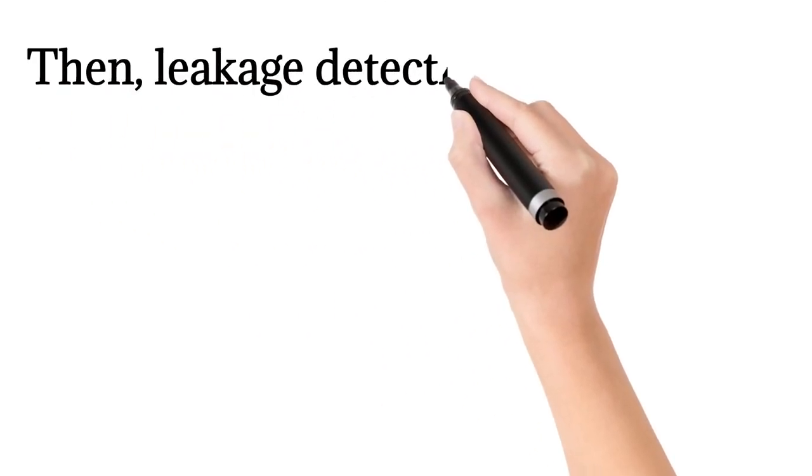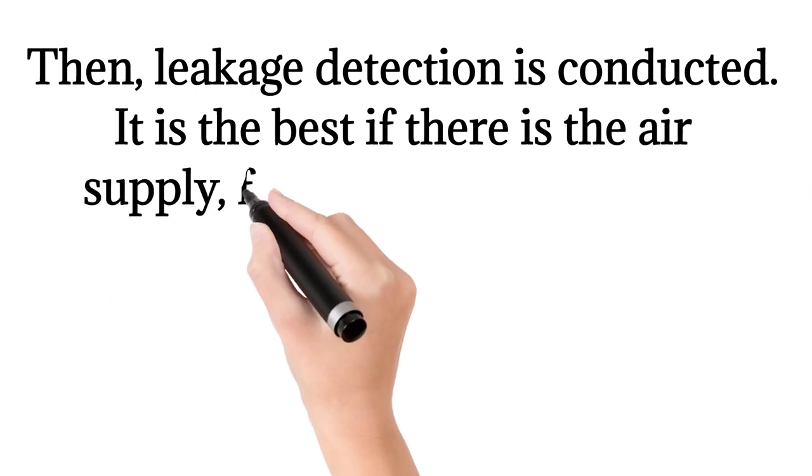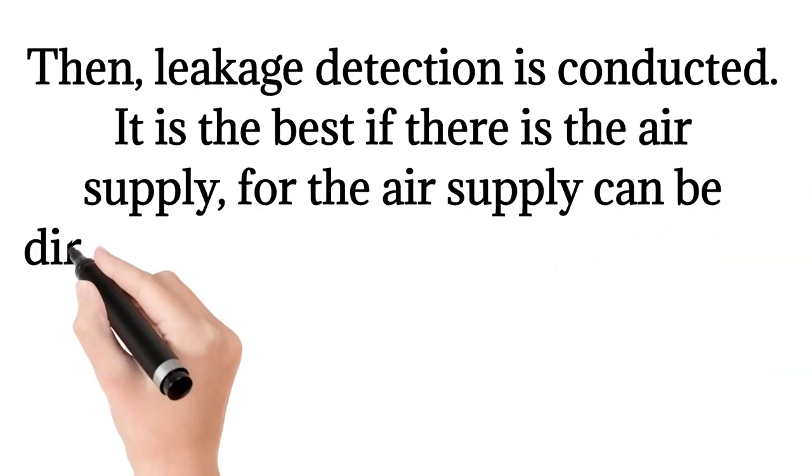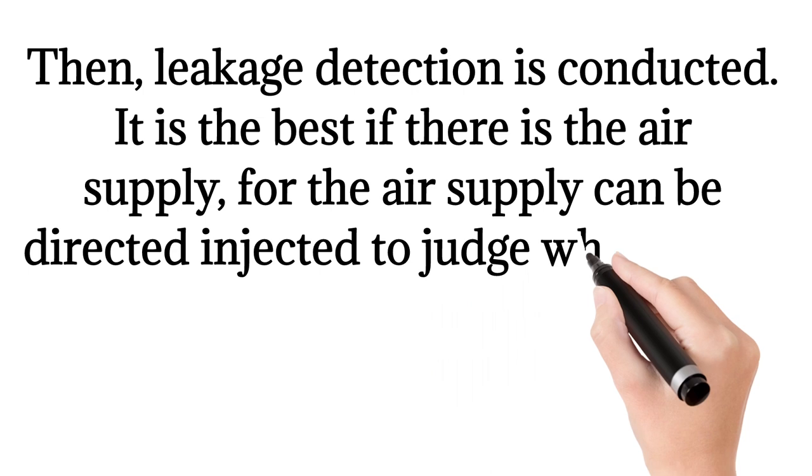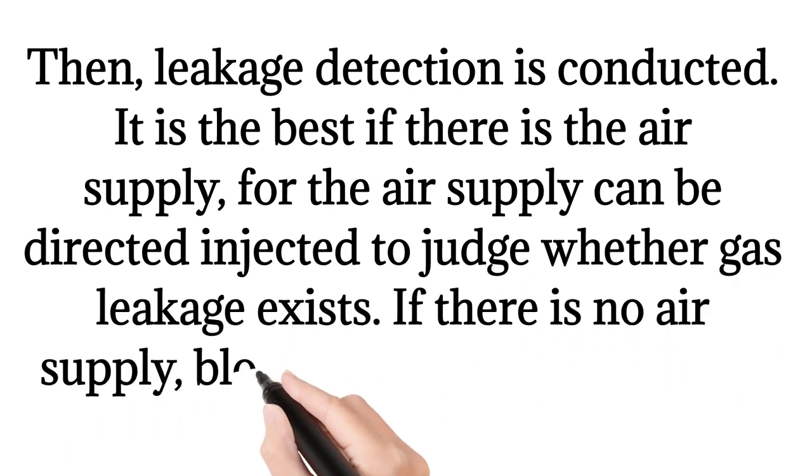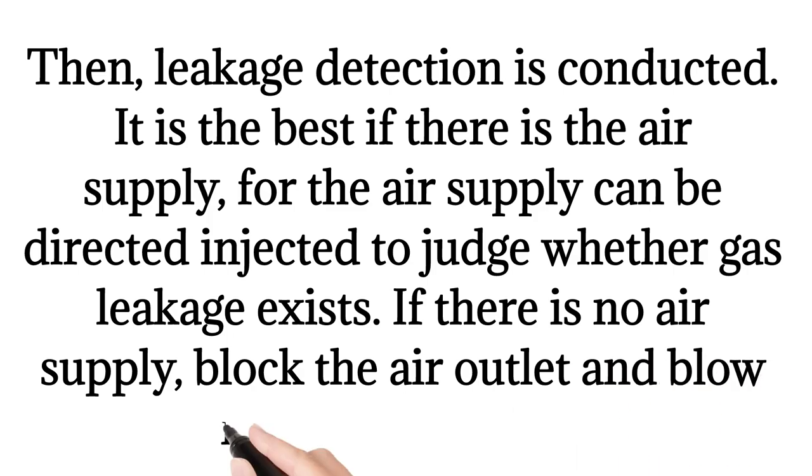Then leakage detection is conducted. It is best if there is an air supply, for the air supply can be directly injected to judge whether gas leakage exists. If there is no air supply, block the air outlet and blow it using the mouth.